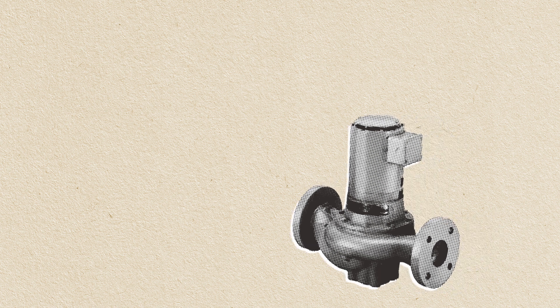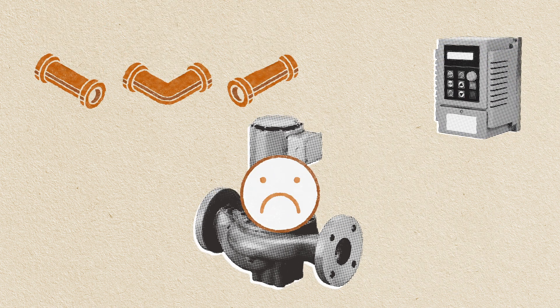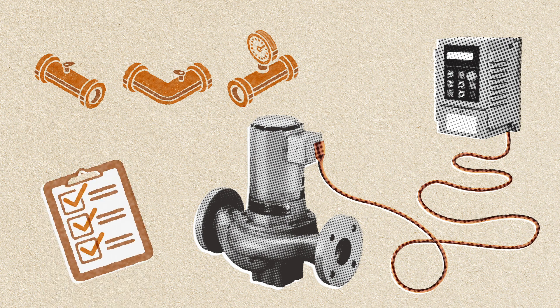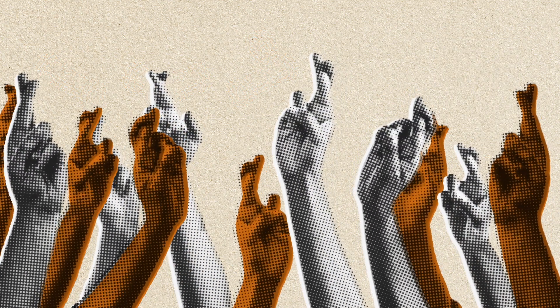The old constant speed pump? Good luck achieving the savings. The VFD and instrumentation would need to be installed separately and won't be calibrated to the actual pump. In fact, a contractor has to mount and wire the variable frequency drive somewhere near the pump, drill into the pipe to install sensors in just the right place, and understand the VFD well enough to program the drive.